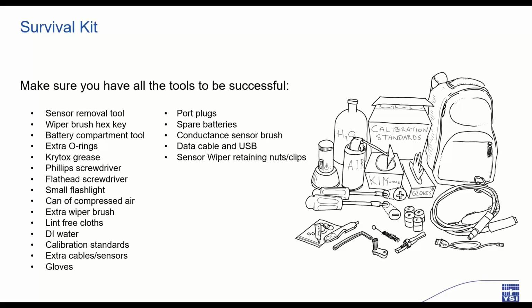In addition, the battery compartment tools, screwdrivers, small flashlight, compressed air, an extra wiper brush, lint-free cloths, DI water, calibration standards might be helpful just in case. Extra cables and sensors may be of use if available. And I always recommend taking some port plugs, which take the place of a sensor when the sensor is not installed. Of course, don't forget spare batteries, and make sure that any items in your kit that have limited shelf life be replenished on a regular basis. There's nothing worse than carrying dead backup batteries in your field survival kit.